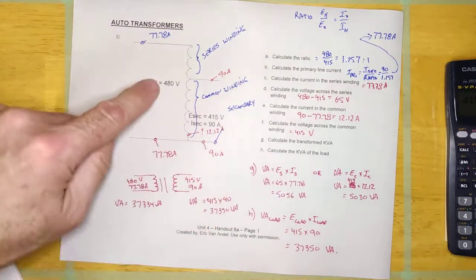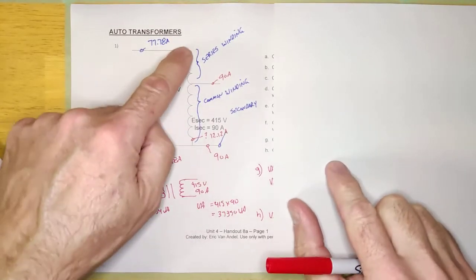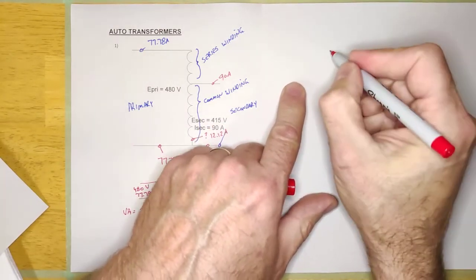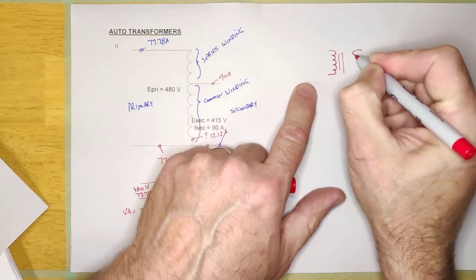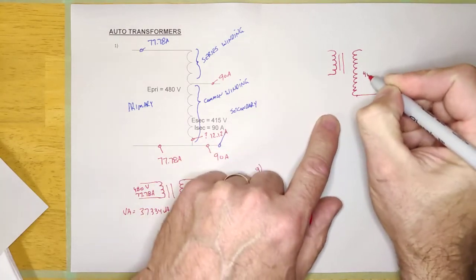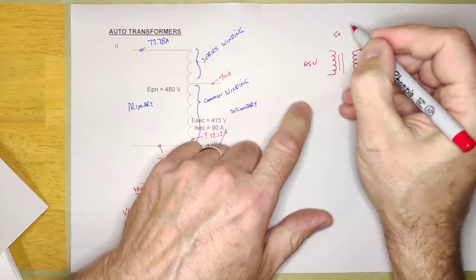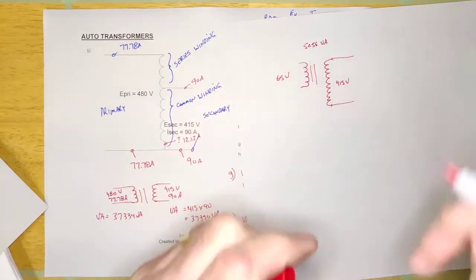And when I say it's made out of — even though every single textbook will show an auto transformer as one winding with a tap coming off of it — in real life it's actually not that way. In real life, they take a conventional 5,000 VA transformer with two windings: this one is 415 volts and this one is 65 volts, and it's rated 5,056 VA.